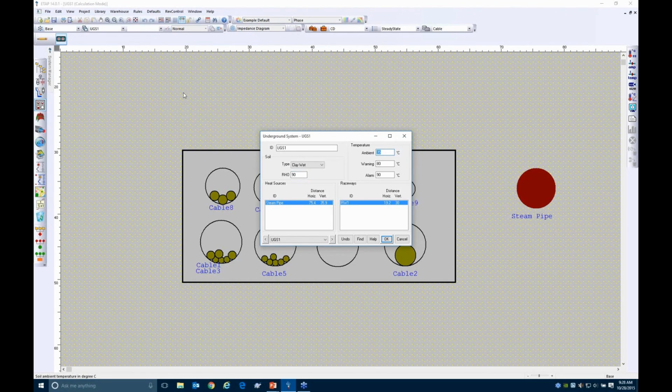We obviously do assume that the soil temperature will increase slightly as it goes towards the surface. However, again, from a conservative point of view, you can either take an average number or the worst case number, and that is going to vary based on summer or winter, or in some areas where you have months of rain, the water may actually drop the temperature even further.